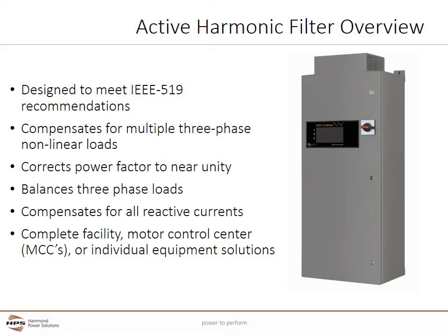One method to mitigate harmonic currents produced by three-phase sources, most commonly variable frequency drives, is to use an active harmonic filter. Active harmonic filters are very similar to a variable frequency drive in the components they have, but rather than powering motors, they are designed to inject harmonic currents that are equal but opposite to the system's harmonic currents to cancel out these harmonics. Active harmonic filters are designed to meet IEEE 519 recommendations and are usually combined with line reactors and DC link chokes at the variable frequency drive. Active harmonic filters compensate for multiple three-phase nonlinear loads.